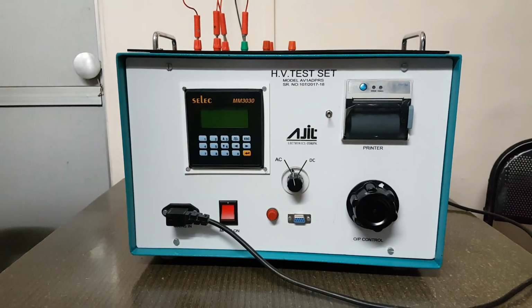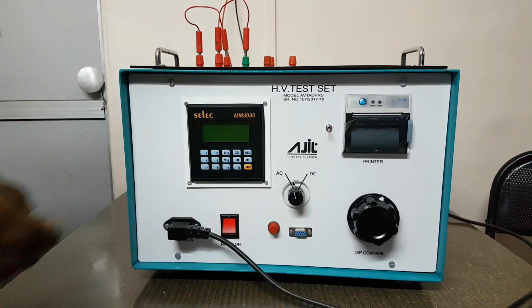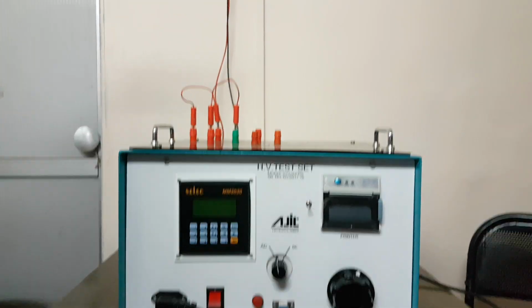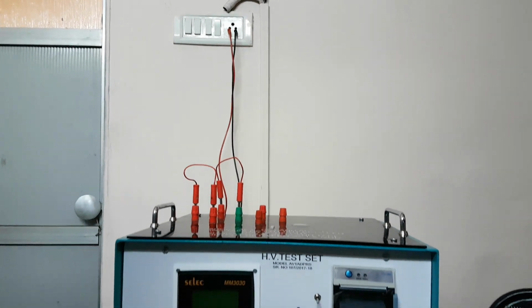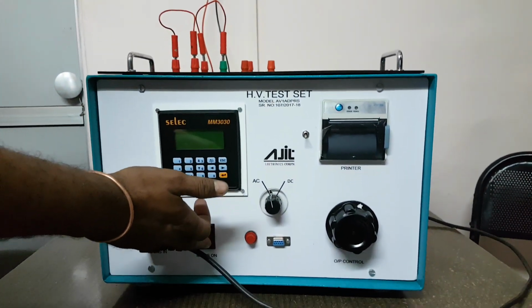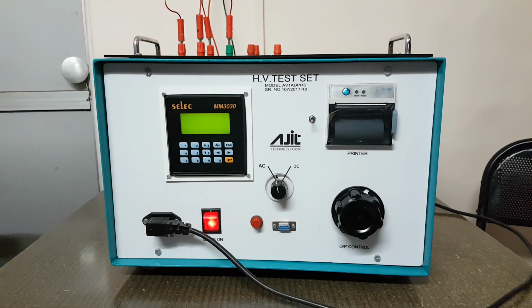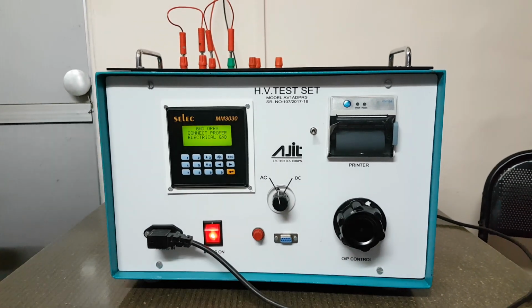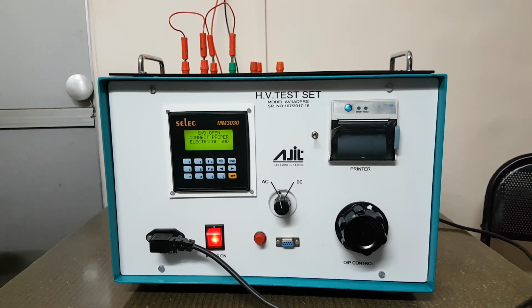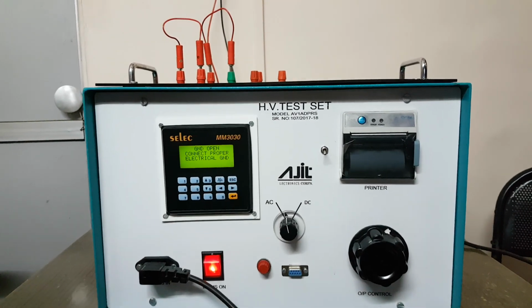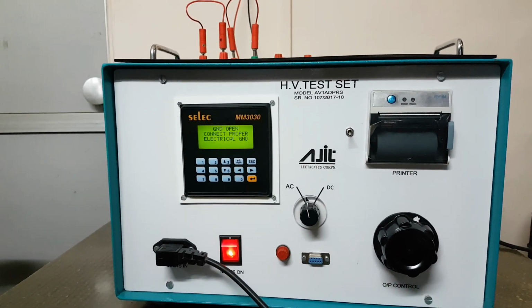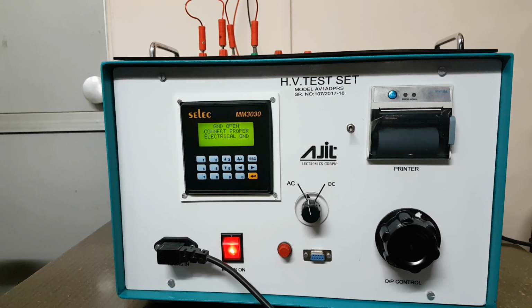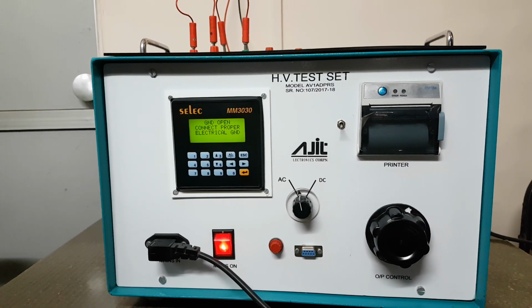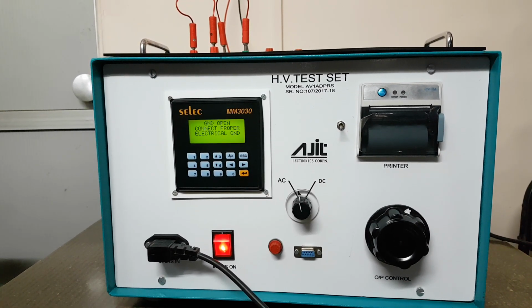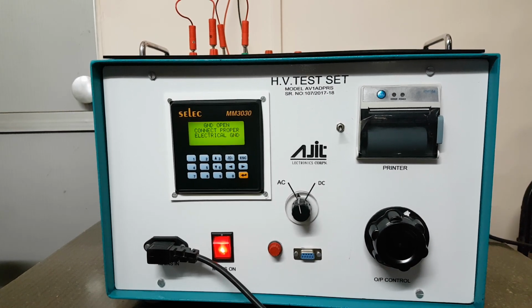Now let's start testing the instrument. We have connected phase and neutral to the instrument from the switchboard. Only two wires we have connected. Now let us switch on the instrument with the mains rocker switch. Here the LCD display is showing that ground is open, connect proper electrical ground.